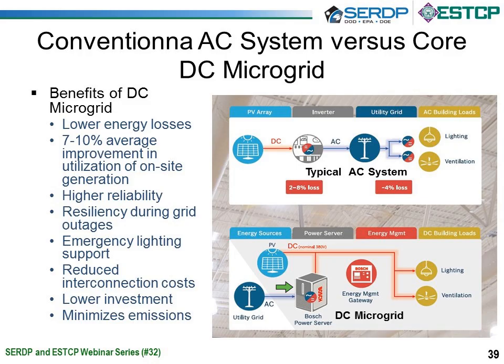So this somewhat comes for free, and it's very dramatic when we do a demonstration of the islanding of a DC microgrid. The lights don't even blink. If the grid shuts off and there's PV available or batteries on the system, the system just keeps operating. There's no switching, no transfer, because the direct current is already connected to the loads.